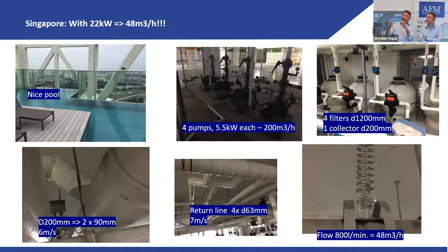And then they came in a piping, really well dimensioned, to DN200 and went to, I don't know how many filters, but at least 4. Diameter 1.2 or maybe 1. So still okay. All okay. 3-inch multi-port valve. So also okay. Or maybe 2.5. So okay on that side.